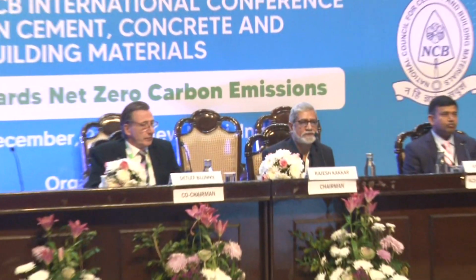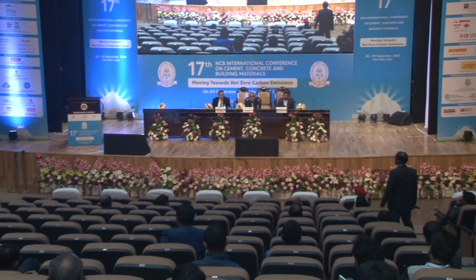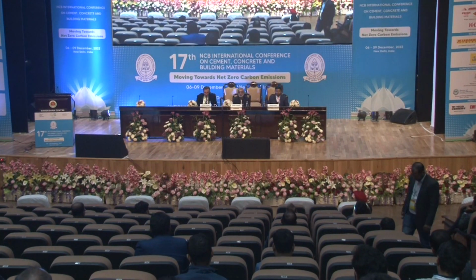So presently we don't have any technology to recover the heat after the cooler boiler, because the temperature is around 80 to 90 degrees centigrade. That can be used only for water heating. We cannot generate any steam from that amount of heat. We have to use it only for water heating, so we have not come across that requirement. Okay, thank you. Maybe you can use that heat to dry the AFRs being used, because converting into power is a very inefficient method. It should be used in the plant itself for drying.